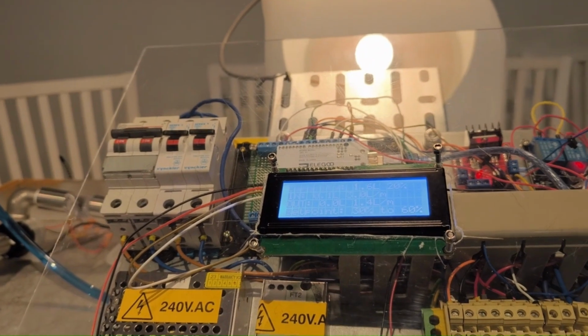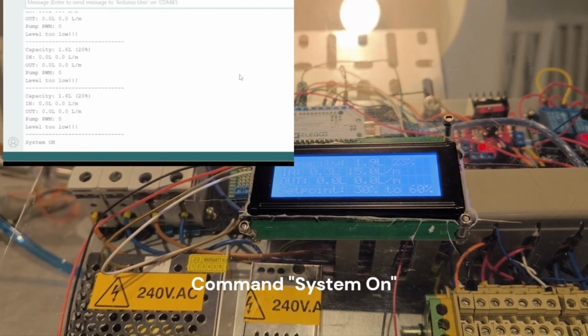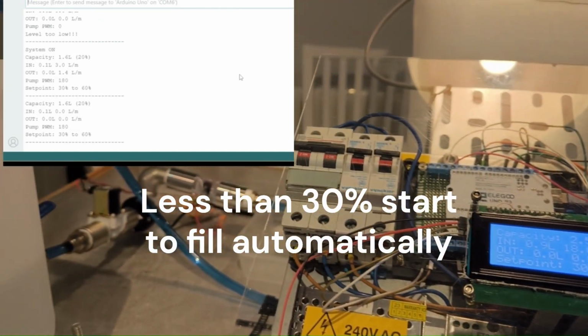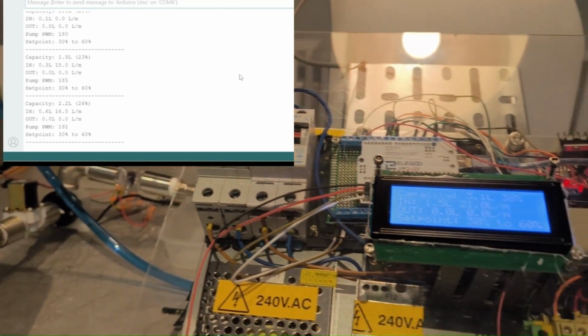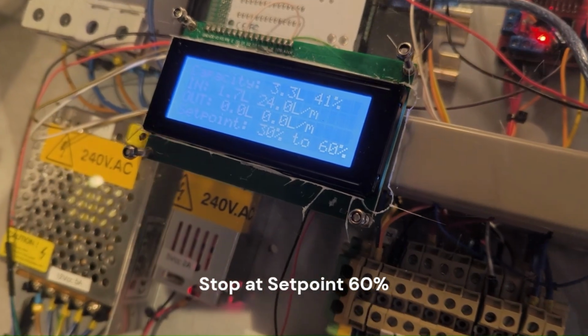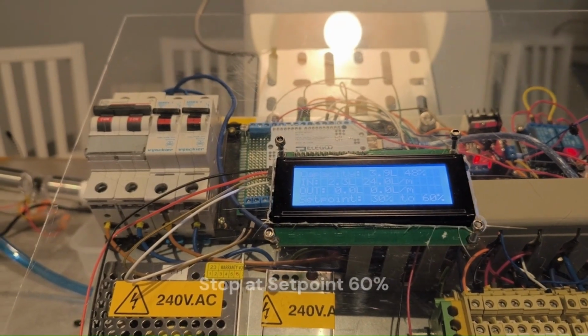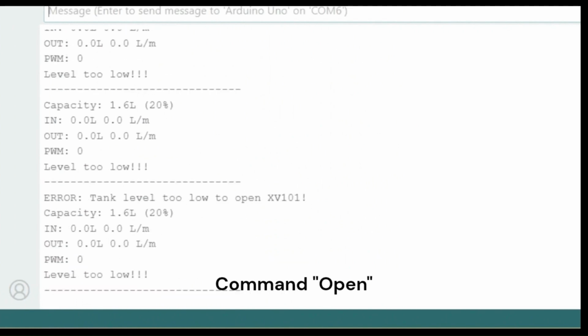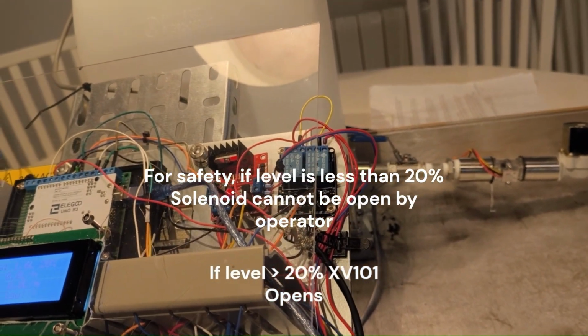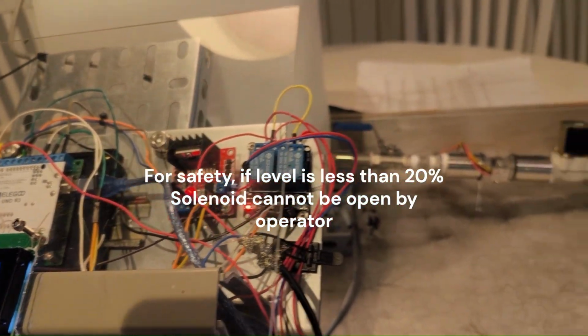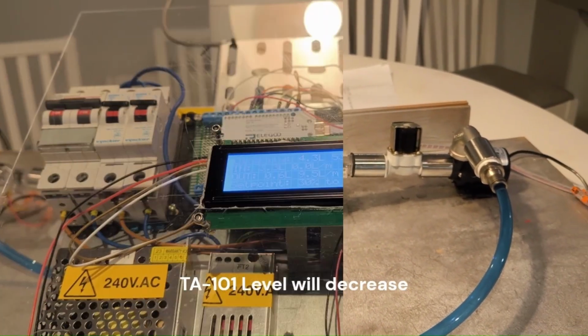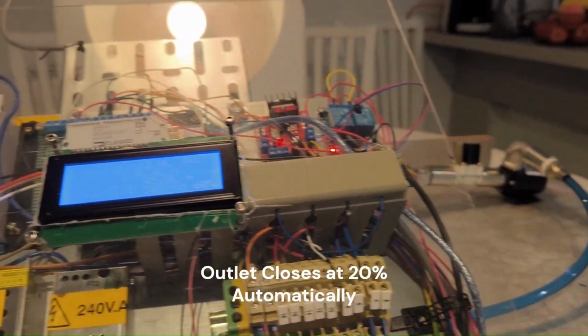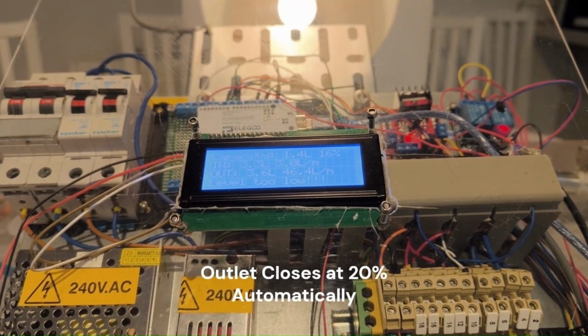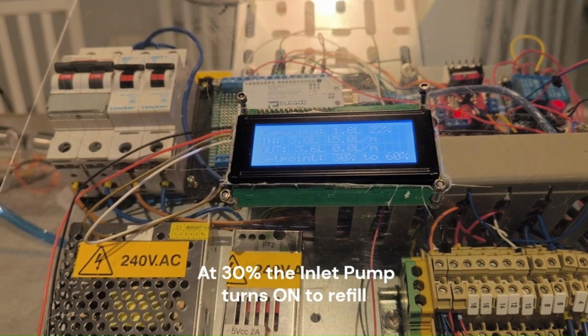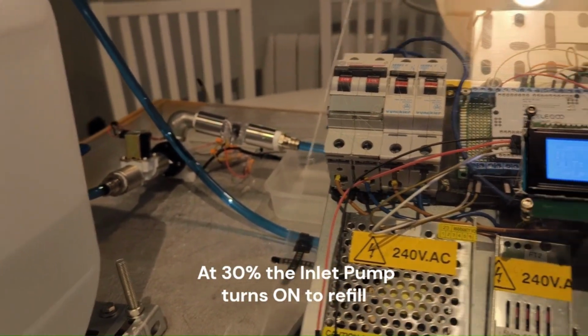So the system will be on with the command system on, and then if less than 30%, we start to fill. The PWM is getting high, started at 185, so the set point is 60%, so we stop at 60%. Stops automatically. When you write the command open, if the level is less than 20%, the pump will not start. If the level is more than 20%, you can open the solenoid valve. When it's less than 20%, it is a safety measure. The pump will not start and the solenoid valve controlled by the operator will close automatically as well.